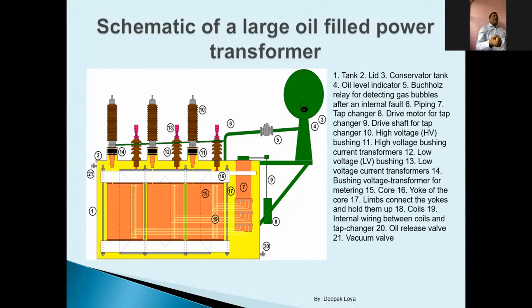Then again, can you measure 5,000 ampere directly in your ammeters? Can you measure 10,000 ampere current through your ammeters? No. So we will need some current transformers for the measurement of the current flowing through the transformer. The current is measured for two purposes. One is for metering and another is for protection. So if the current is more than the rated current of this transformer, then this transformer should be tripped. That means either it is an overloading condition or it is a fault. You might have learned the protection system, so I will not enter into that in detail. But what I want to say is, there has to be some CTs to measure the current.